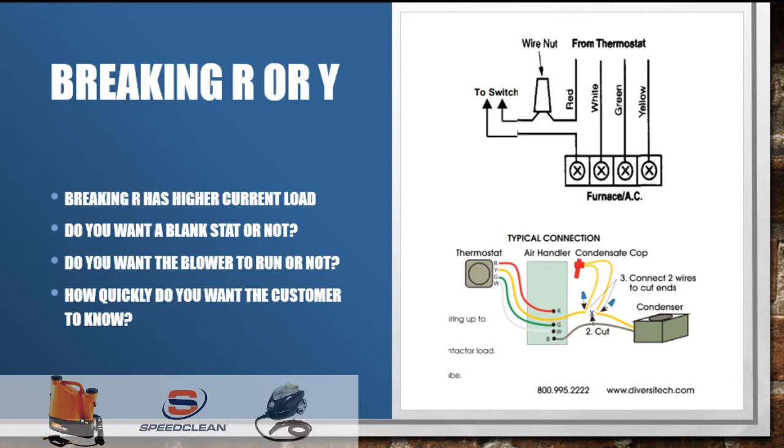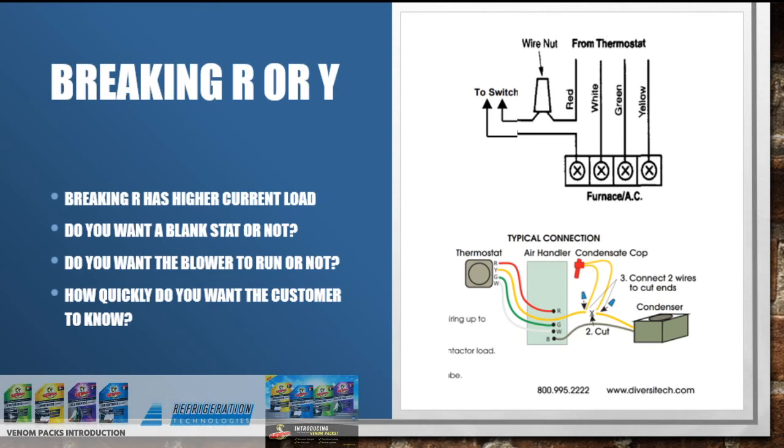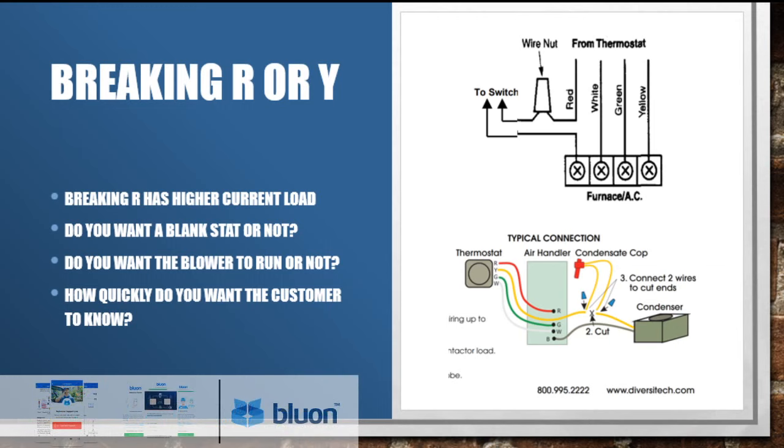And the reason is that as you have thermostats that have more and more settings, you run the risk of it losing those settings when you have power off. But even more than that, the customer just has the assumption that if it's supposed to have batteries, it needs to have batteries in it. And I've seen nuisance service calls just associated with customers getting cranky because you don't put the batteries in.